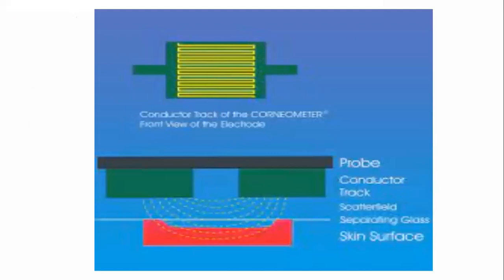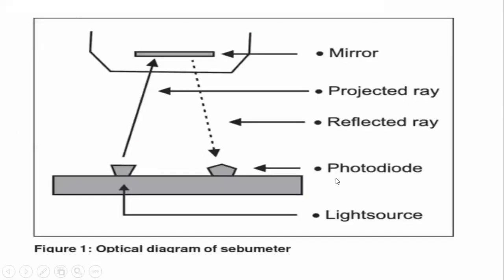The instrument consists of a mirror-like structure inside the device. After placing the cassette, it transmits a projected ray that touches the sebum film or sebum layer on the cassette tape. The ray is then transmitted through the tape and sebum film and reflected back, where it is caught by a photodiode. The principle is similar to a spectrophotometer — the amount of reflected ray measures the amount of sebum present.